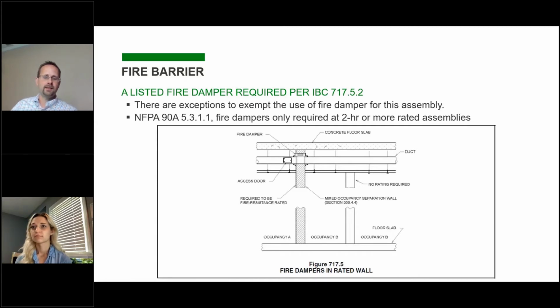What we found, the typical interpretation of this is if you're fully ducted with that 26 gauge, and then you have a short run of flex duct to your diffuser, which is very common on supply systems in a lot of areas, that still qualifies for this exception, so you don't have to have fire dampers.